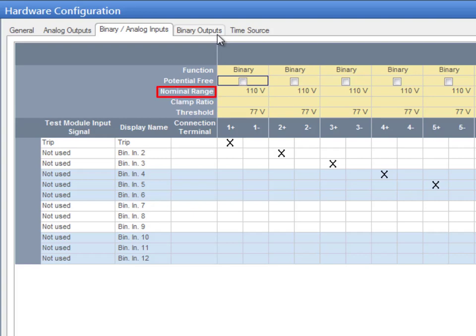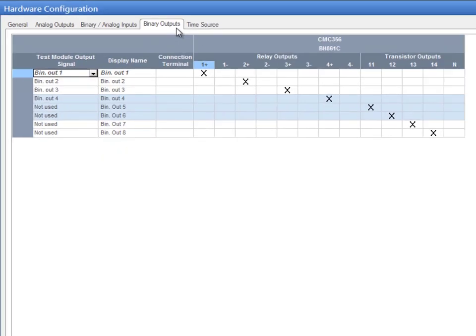Nominal range represents the nominal voltage of potential sensing binary or counter inputs, or the nominal range of analog voltage or current inputs. Threshold indicates the limit for potential sensing binary or counter inputs. Apply the same theory to configure the Binary Outputs tab.